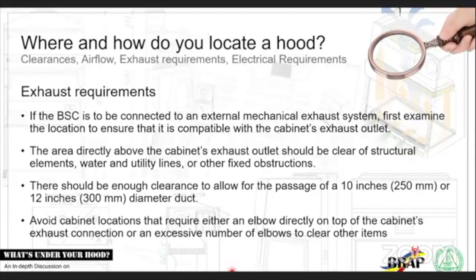Now, exhaust requirements. If your biosafety cabinet requires ducting, you should consider that. Your Class 2A2 doesn't have a blower strong enough to blow your dirty air up your ducting and into your exhaust ducting. There are always mechanical exhaust systems for your external ducting. All right? Now, if you're going to ask me the standard airflow for your exhaust, well, it depends on what you want to have in your environment, which again goes back to your risk assessment. Okay?